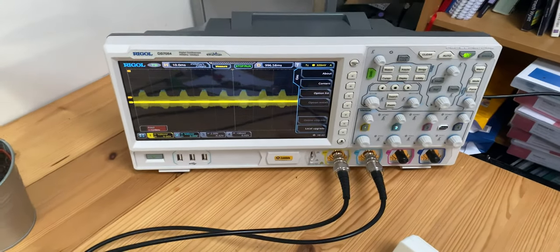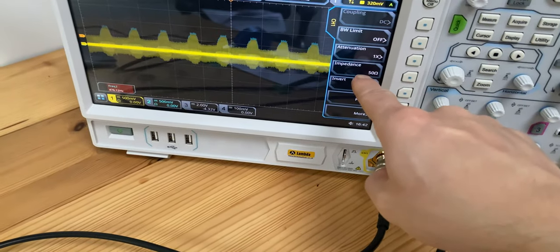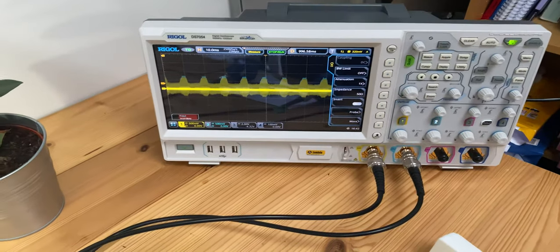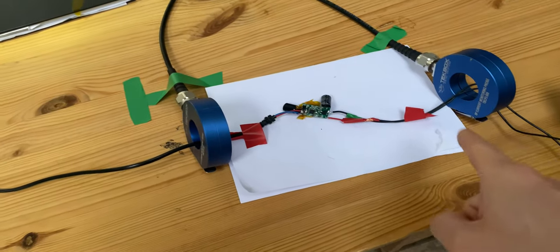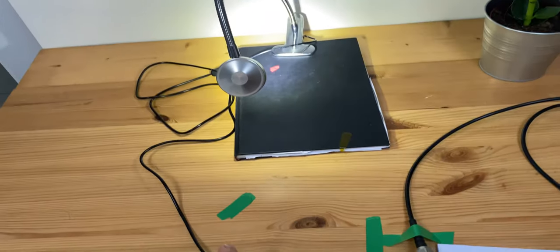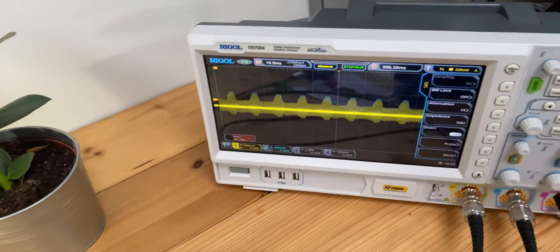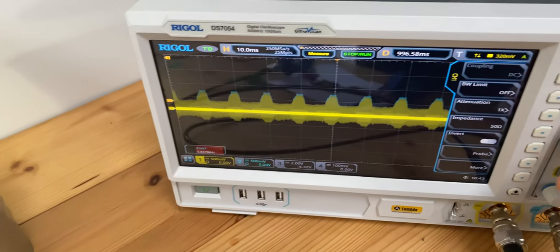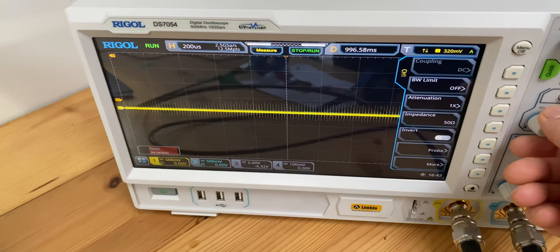The two current probes in this case are connected to an oscilloscope. Note that in this case, we need to change the oscilloscope impedance to be 50 ohms to pick up the signal. As you can see here, because we're measuring the common mode current goes into the power supply and comes out of the power supply. So these two, as you can see from the results here, they pretty much picked up exactly the same signals.